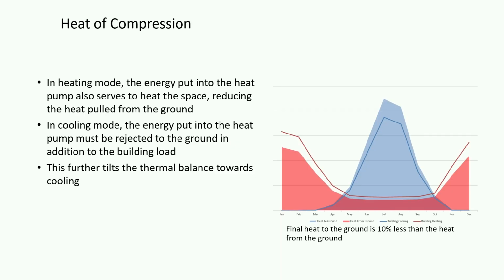Innate to a heat pump, you have to contend with heat of compression. So for a heat pump, you have to put energy in to move energy around. If you are heating, that energy that you put in is contributing to heating your space. If you're in cooling, that energy you put in, you also have to get rid of. So when we look at what's actually finally making it to the ground in a geothermal system, you have a gain, so you won't have to pull as much heat out of the ground in heating because you have that additional, and then in cooling, the reverse.